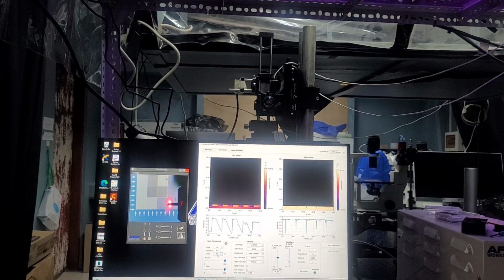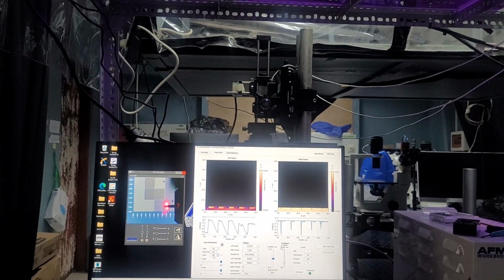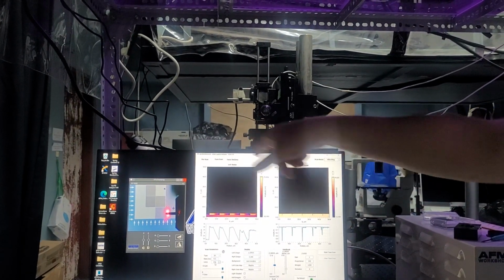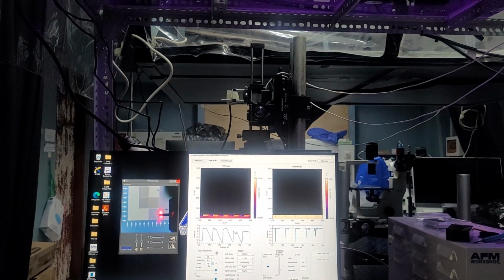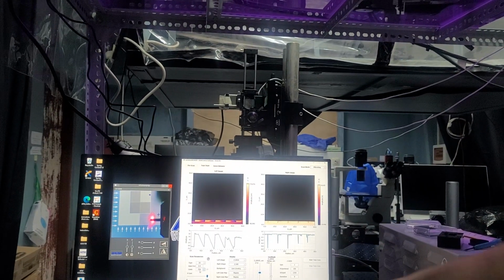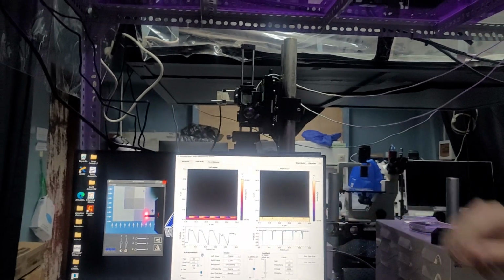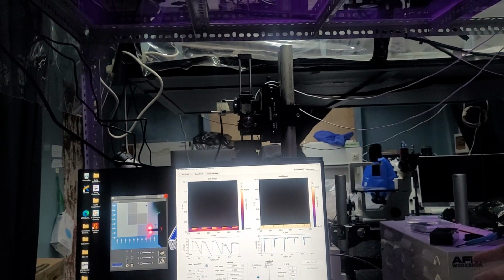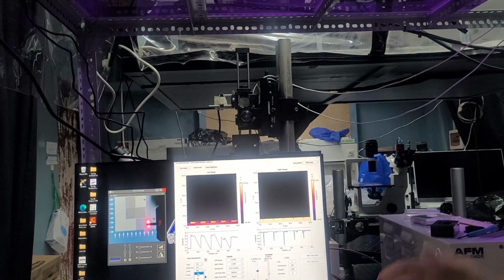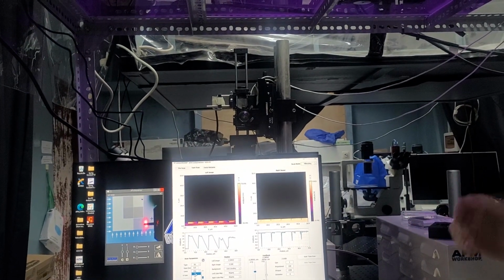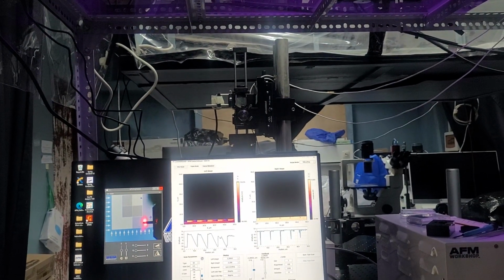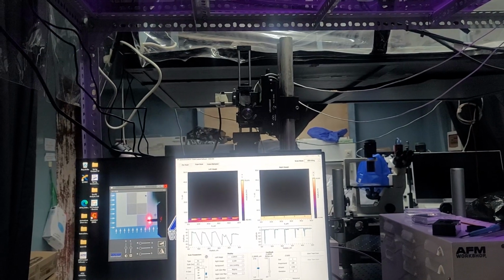Below that is lines. This will control the pixel density of your image. So it's essentially how many times that cantilever will go back and forth across the sample surface. The default for this is 256. That is 256 lines and 256 average data points per line. So it creates a 256 by 256 pixel image. It can go anywhere from 16 by 16, which over a 50 micron scan you're not really going to see much, all the way to a 1024 by 1024. I recommend sticking to 256 and 512.